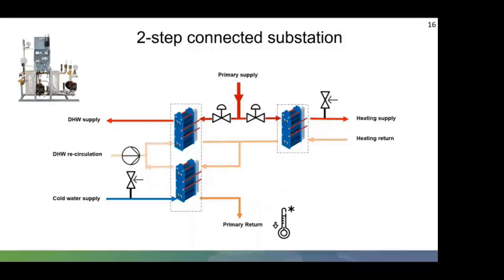Using a 2-step connection takes latent heat and preheats the domestic hot water heat exchanger. Not only does this decrease the time to heat the hot water initially, it also aids in reducing the primary return temperatures. So it acts as a heat dump to a certain extent. So when it returns back into the district heat network, it's a lower flow again. So again, you're extracting the maximum amount of heat out of the flow that's coming into the building. So making it more energy efficient. There's no waste energy.